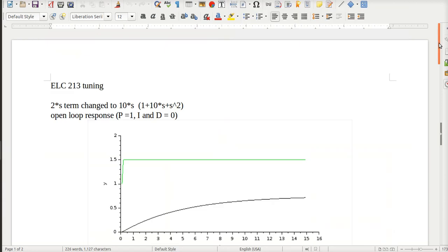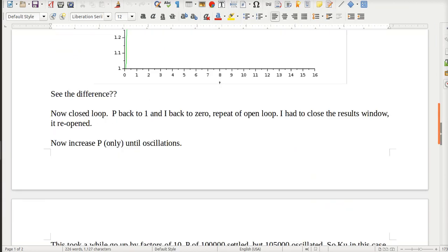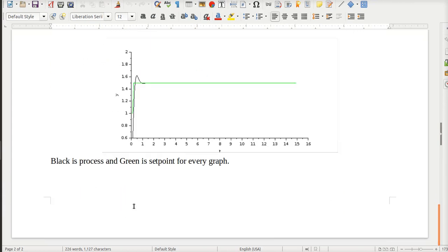So let's go down to the bottom. What did we say our delay was? So I'm going to edit this document. So our step time was 50%. Our R is 0.48 over 1, or 0.48. And our delay time was like 0.35. Okay, so that's going to give me tuning constants, if you will.